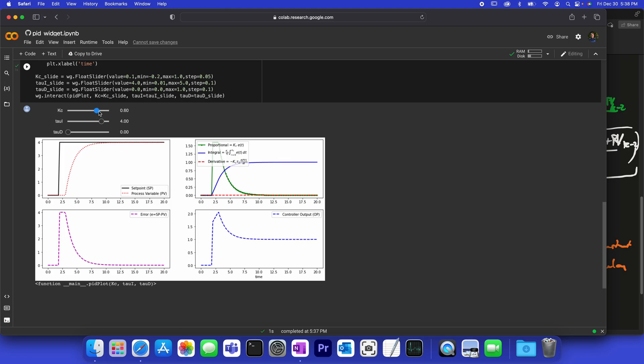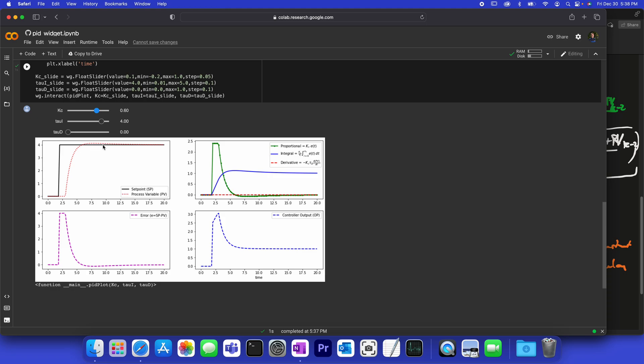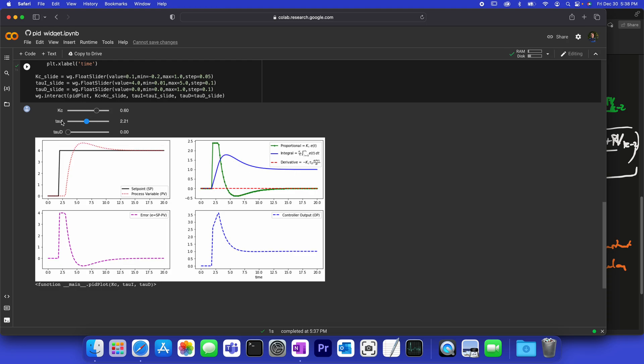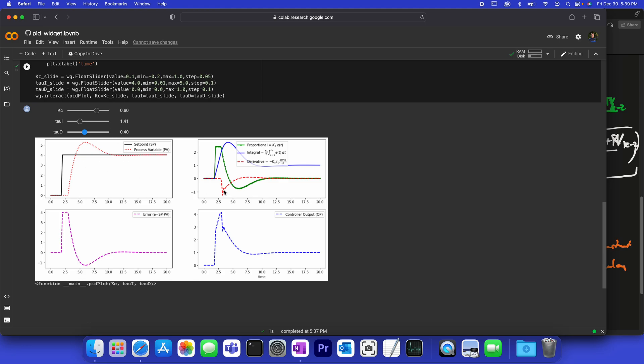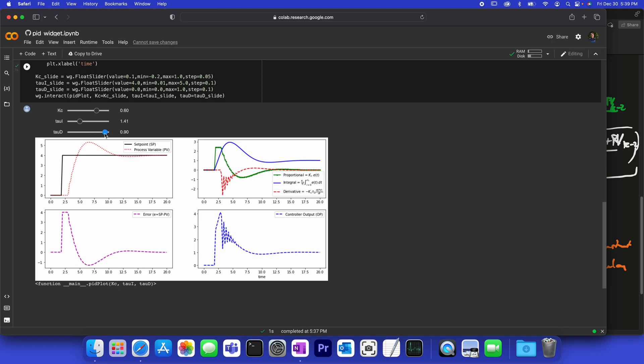Let's start increasing the gain further to see how fast we can get it. We see a little bit of overshoot starting to happen. If we decrease the integral time constant (which is in the denominator, so the integral term gets bigger), we can see that integral term grow. The proportional term goes negative once overshoot starts. Adding derivative: as the PV approaches the set point at high slope, the derivative says 'I'm approaching too fast, let me back off.' However, too much derivative can cause noise amplification or instability in the controller output.